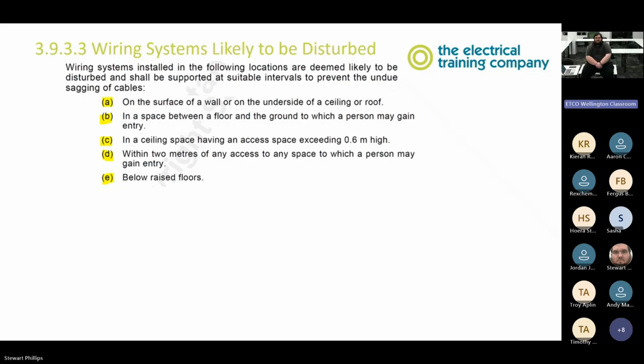So these are situations where cables are deemed likely to be disturbed. So they need to be supported at suitable intervals to prevent undue sagging. So on the surface of a wall or on the underside of a ceiling or roof. So when you're running it along the surface of a wall or along a ceiling or along a roof or under the roof, and a space between the floor and the ground to which a person may gain entry. So the basement and the ceiling space. So if the ceiling space has an access space exceeding 0.6 meters high, so basically you can crawl around inside it, you need to make sure the cables have adequate support. And within 2 meters of any access to any space, so within 2 meters of the manhole, within 2 meters of the door into the basement, and below any raised floors. So a raised floor, for example, inside of a plant where the floor is raised off the ground.